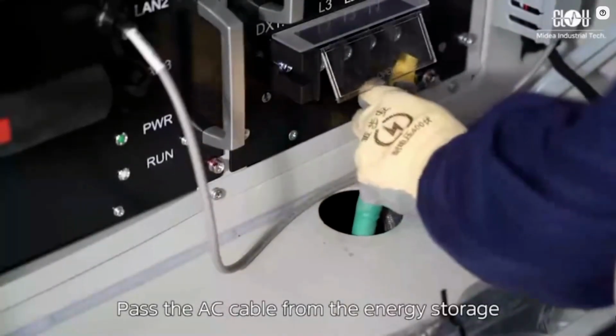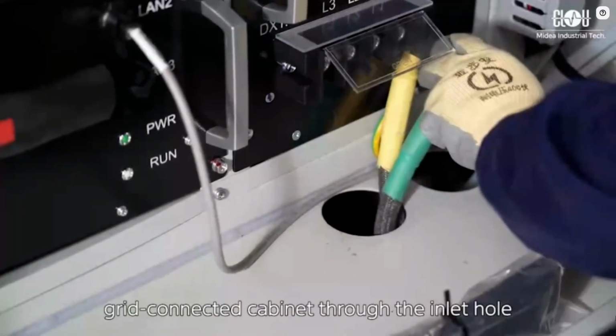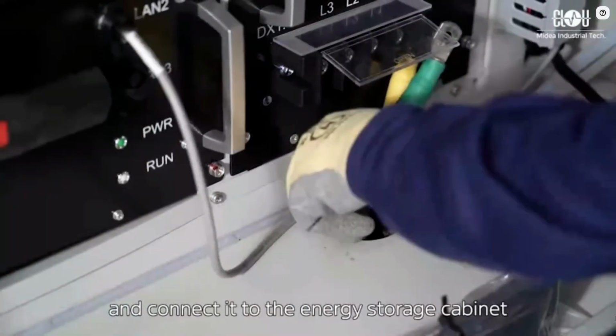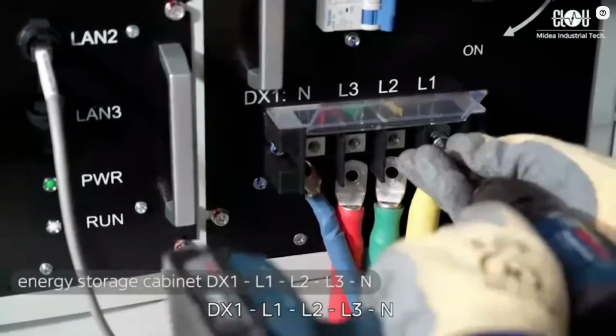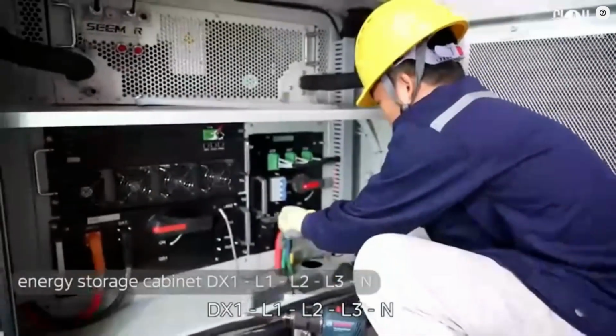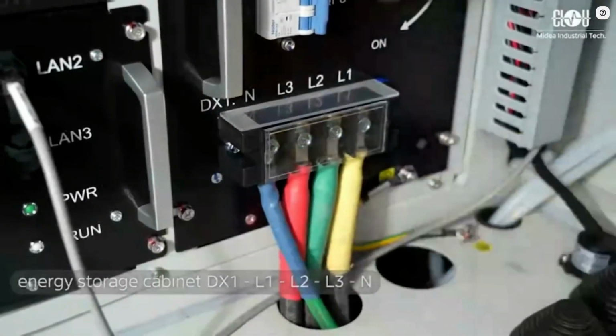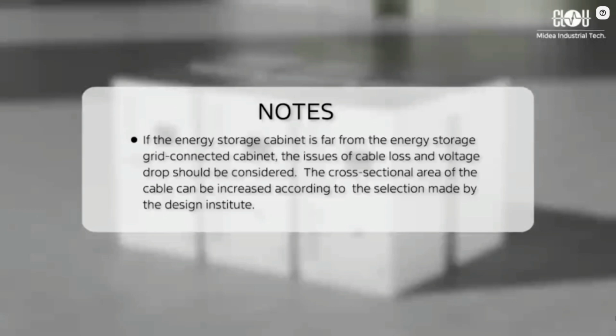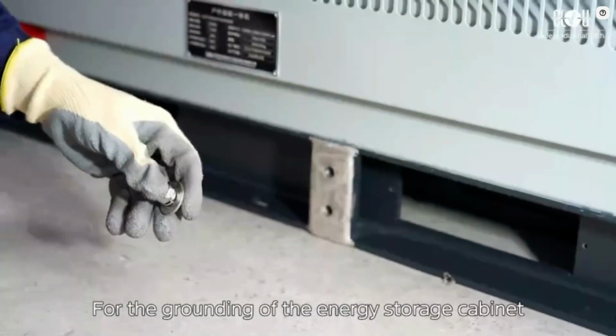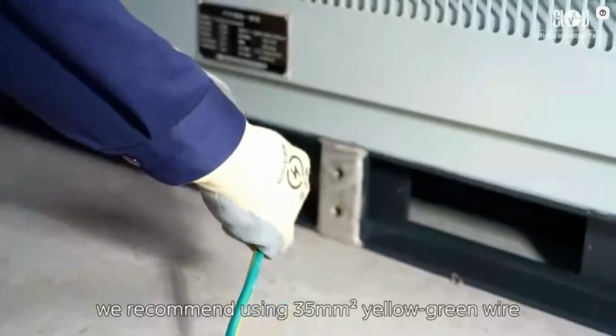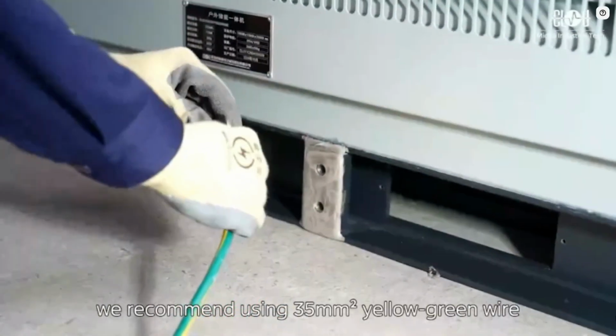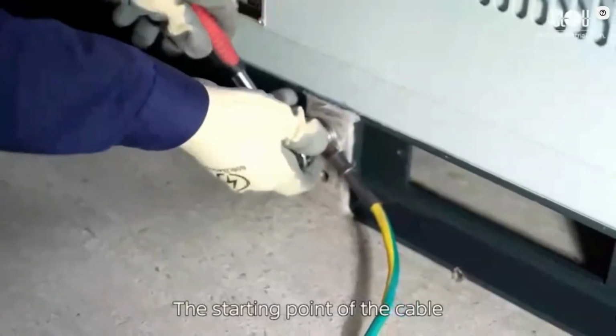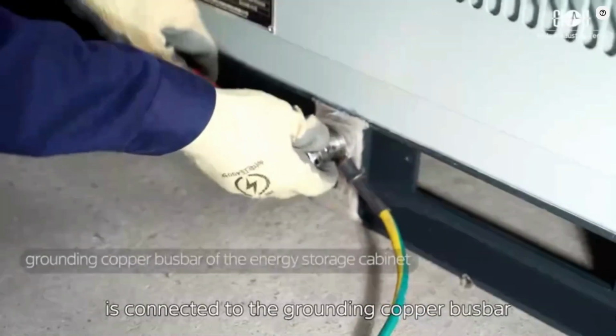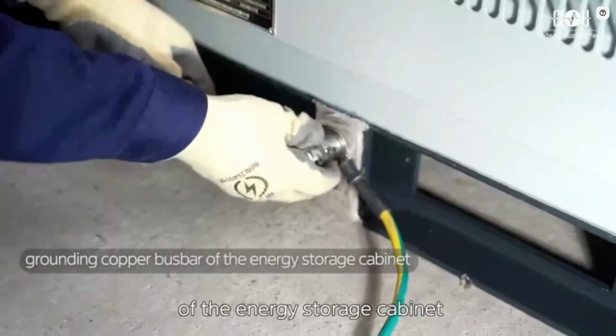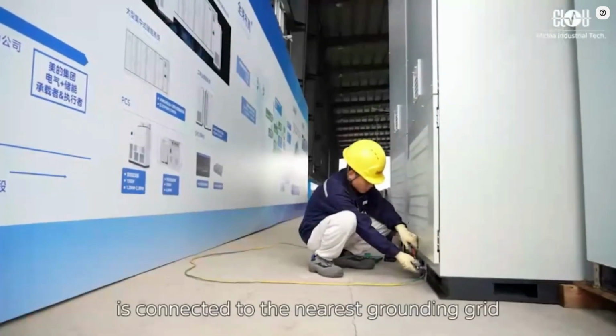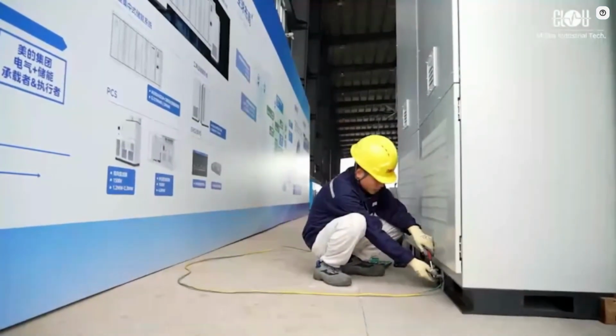Pass the AC cable from the energy storage grid-connected cabinet through the inlet hole and connect it to the energy storage cabinet DX1, L1, L2, L3, N. For the grounding of the energy storage cabinet, we recommend using 35 square millimeters yellow-green wire. The starting point of the cable is connected to the grounding copper busbar of the energy storage cabinet, and the endpoint of the cable is connected to the nearest grounding grid.